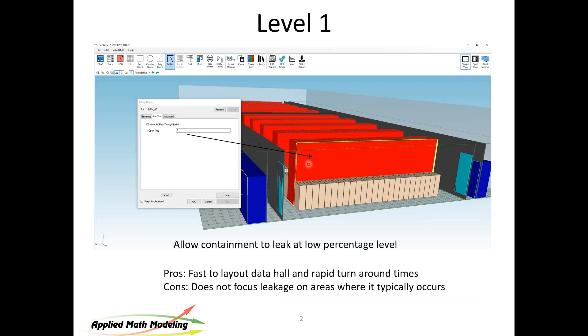Level one leakage modeling simply allows the containment to leak at a certain percentage — for example 5%. This is a quick way to model large data centers where you let the containment surface leak, typically on the vertical sides but not on the end caps. You use CoolSim's rack row concept where you put in a count, set a rack size, and it lays them in assuming no inter-rack leakage. It's fast but doesn't focus leakage on the area where it really occurs — down low at the rack perimeter.